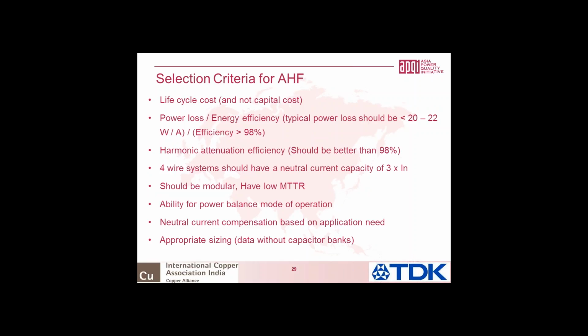per amp. For example, if you go back to the capacitor, which is a very, very efficient device, capacitor is one of the most efficient devices. On every purchase, be it industrial, utility, tendered or untendered, they say the watt loss must be less than 0.2 watts per kVAR. 0.2 watts per kVAR is 99.98% efficiency, right? Whereas when we buy an active filter, which is much more lossy, nobody seems to be interested in specifying the watt loss. In our estimate, it should be less than 22 watts per ampere.